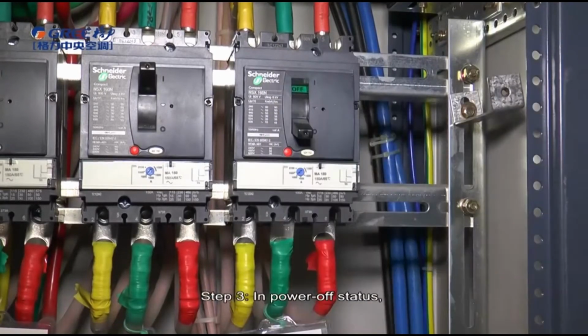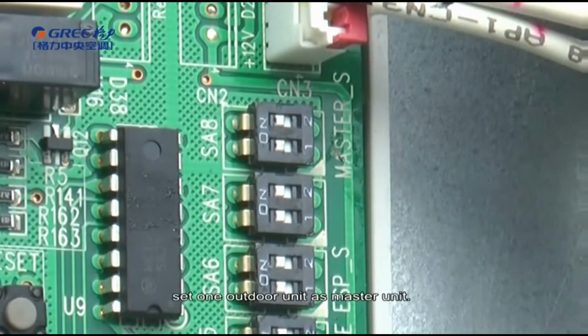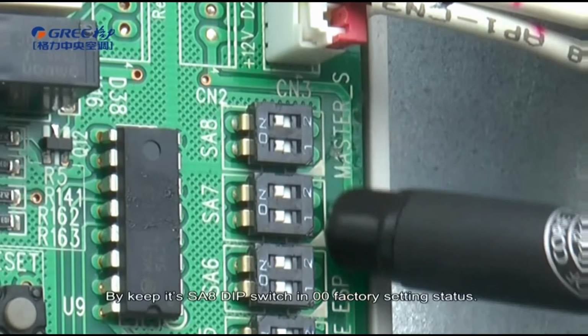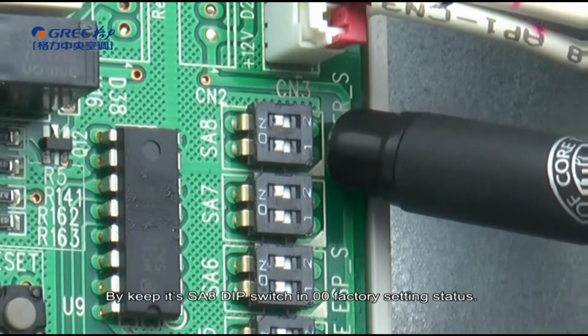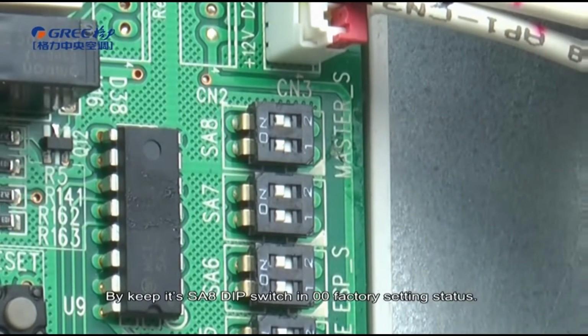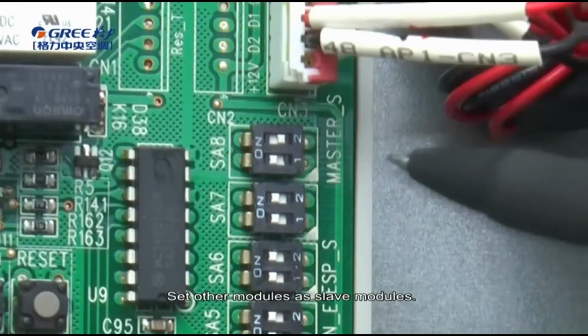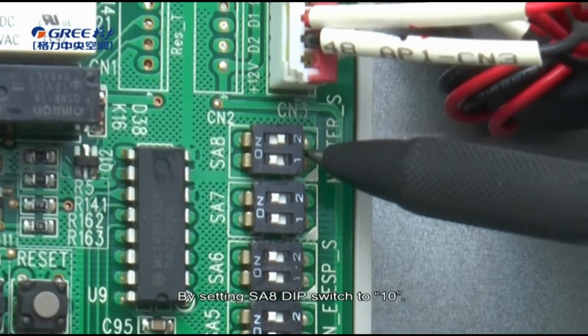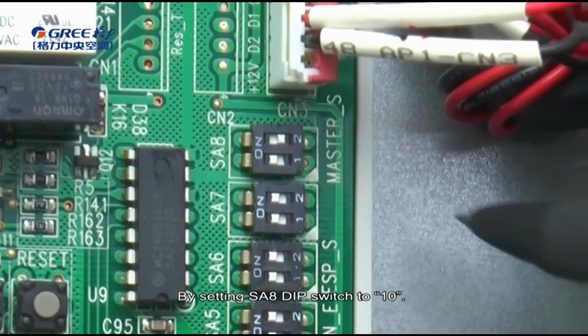In power off status, set one outdoor unit as master unit by keeping its SA8 dip switch in 00 factory setting status. Set other modules as slave modules by setting SA8 dip switch to 10.